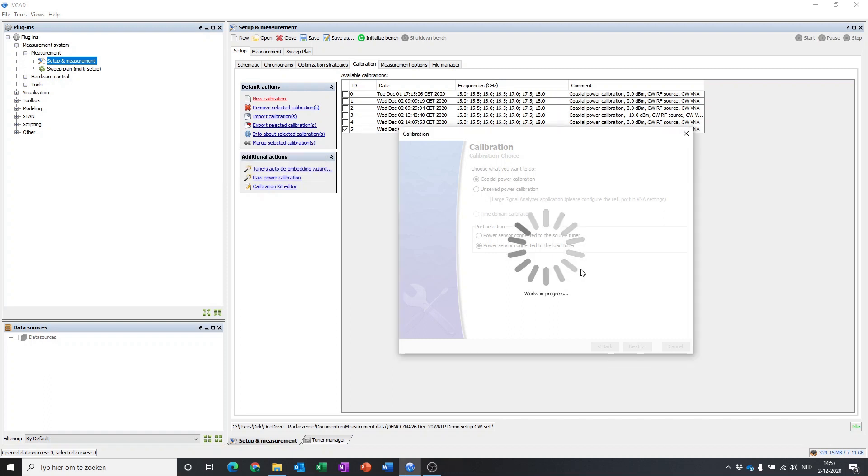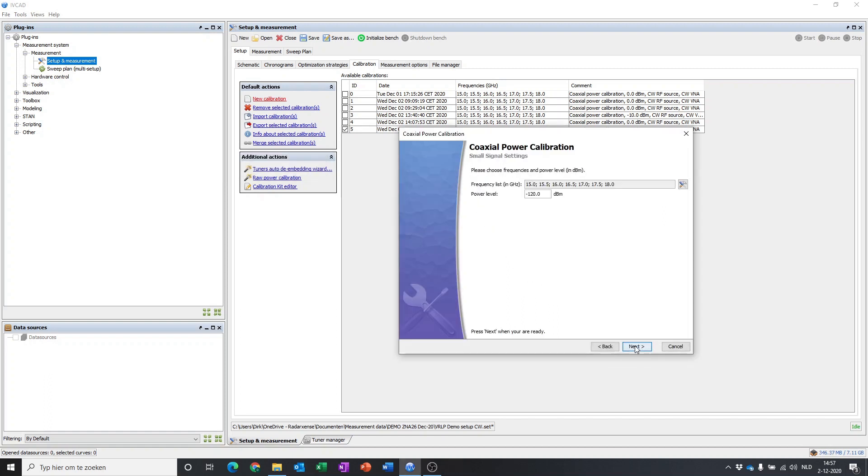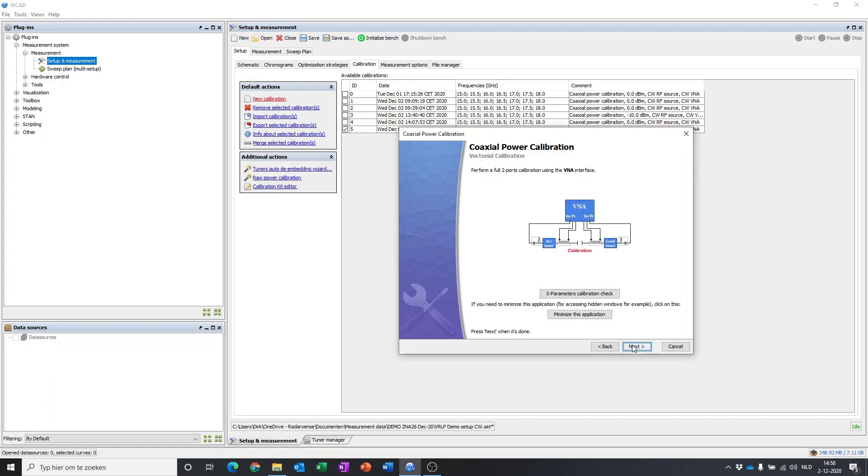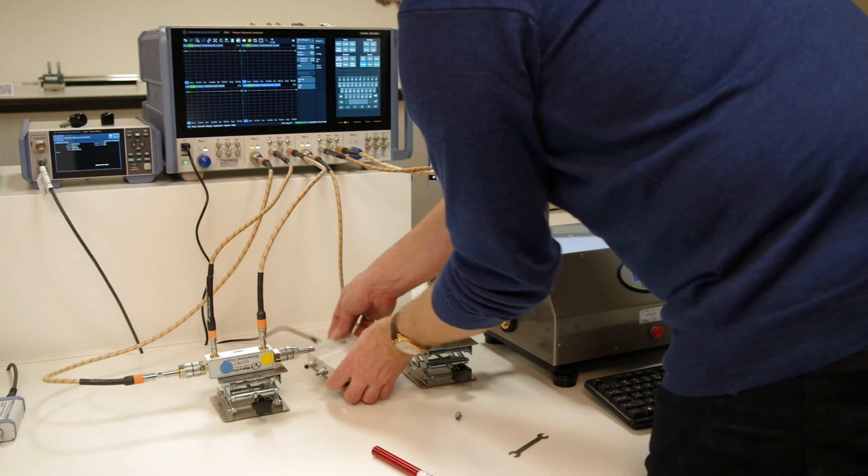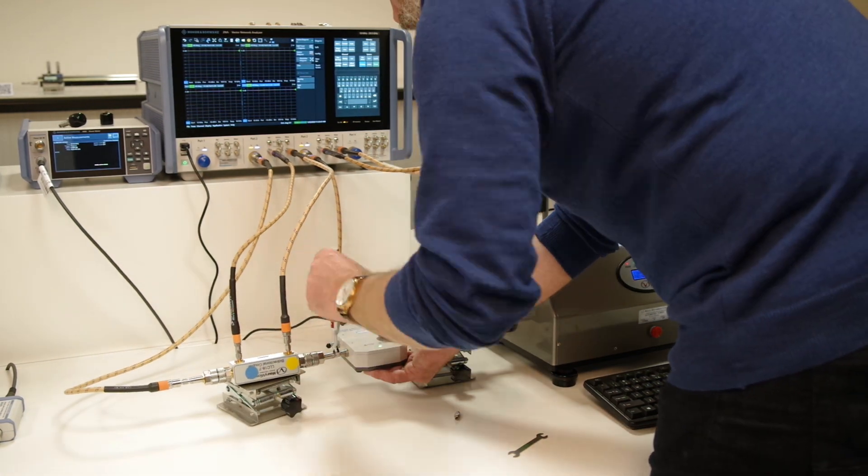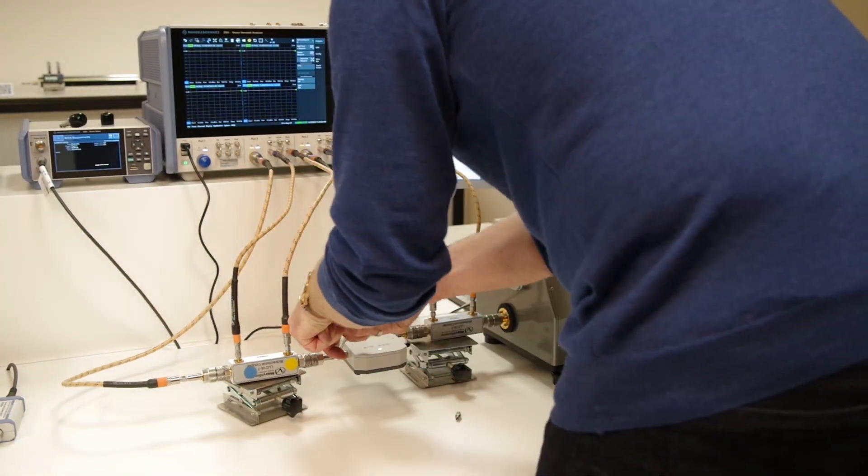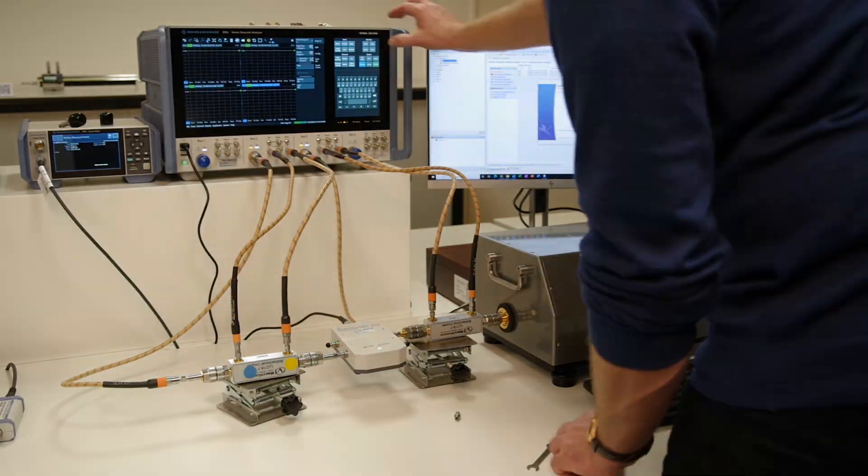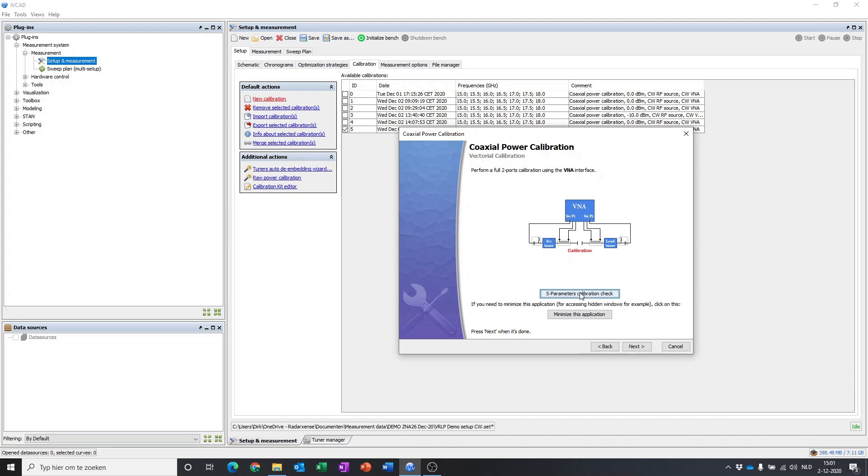Like any other configuration that includes a vector network analyzer, a vector receiver load pull setup needs to be calibrated. The calibration routine is guided by the software, which gives no room for making mistakes.